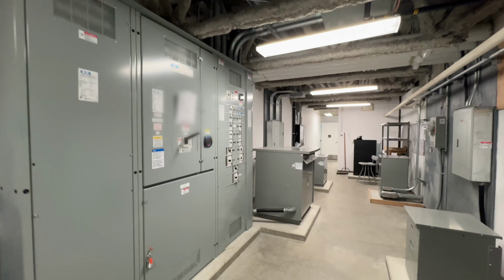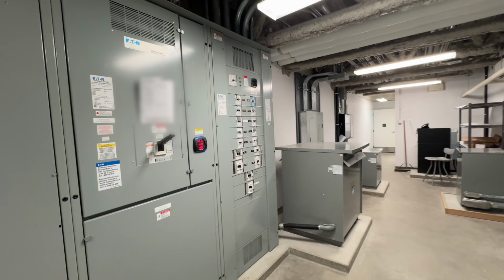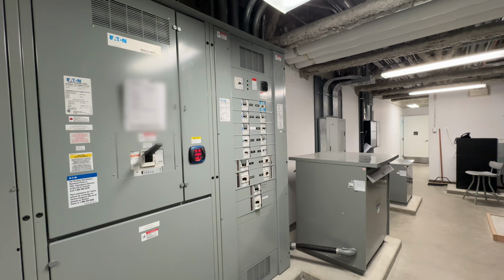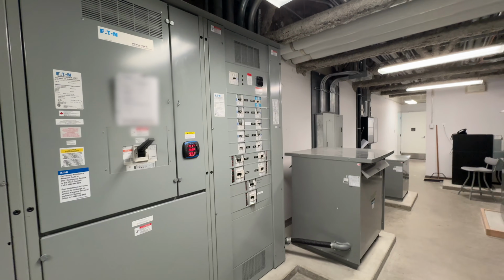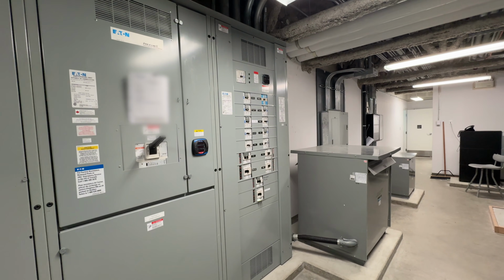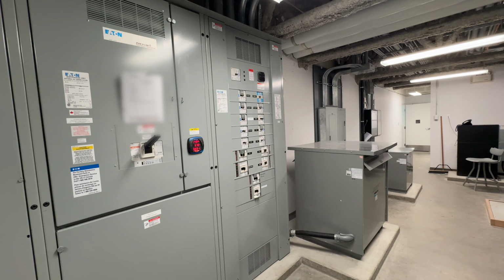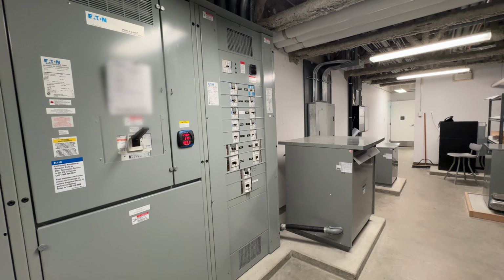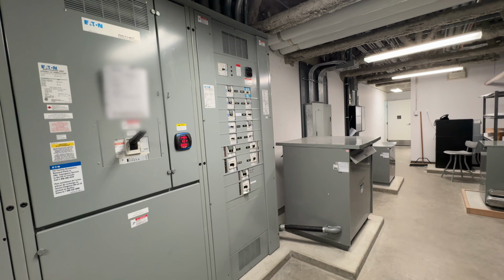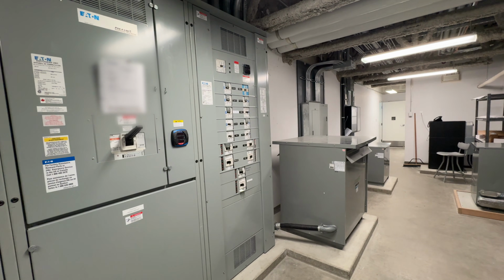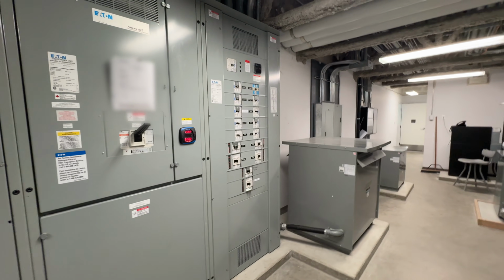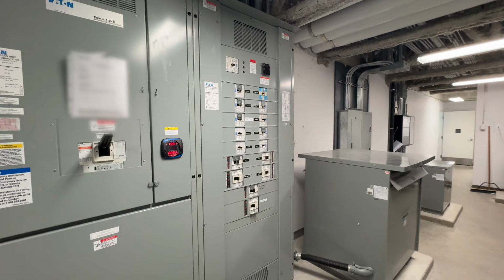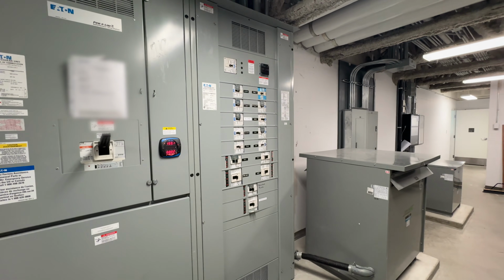So now we have entered the time before switching back to utility power. Basically, this is a power outage. Power has just come back on, but we're still running on generator power for a little bit. So we have to wait until the generator has its utility delay over. Basically waiting, making sure that utility power is stable. There's no sense of turning off the generator back onto utility power if that power is not a stable source.